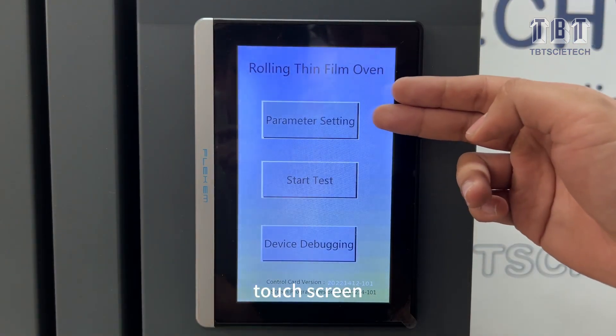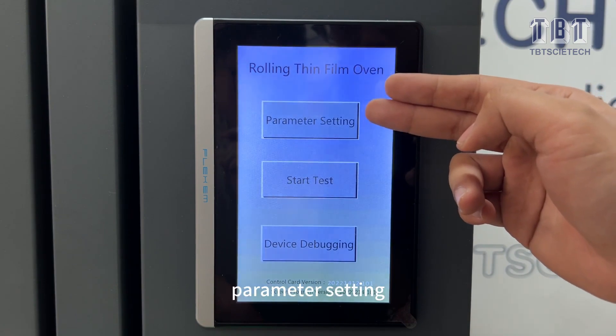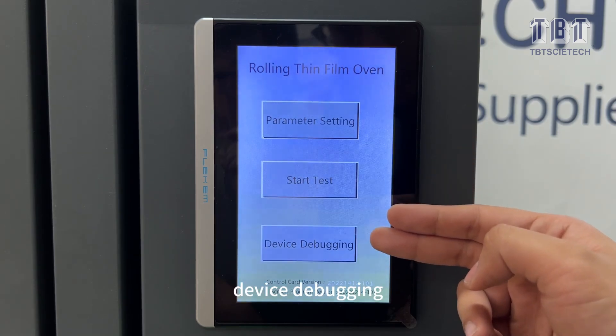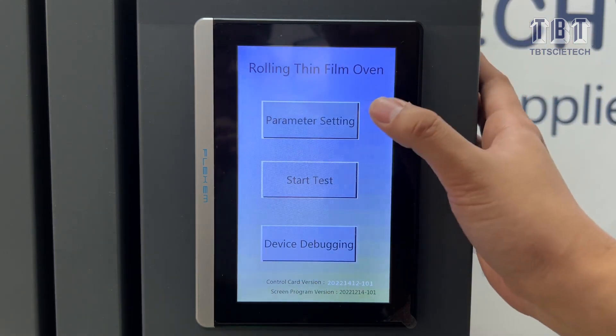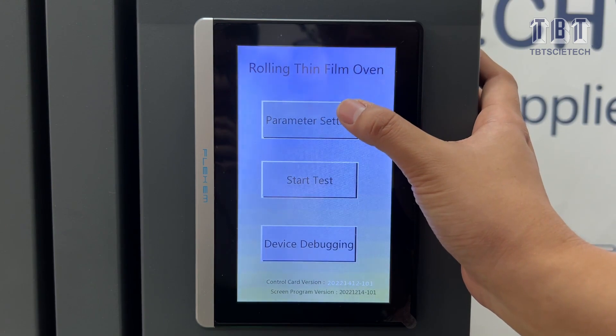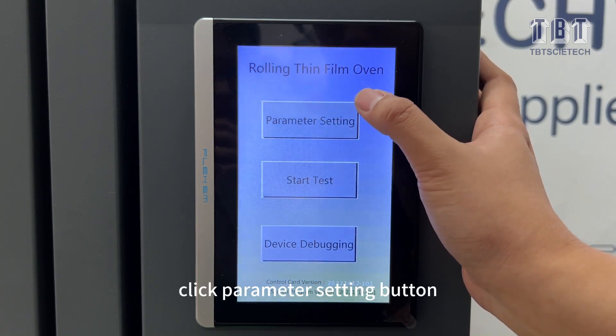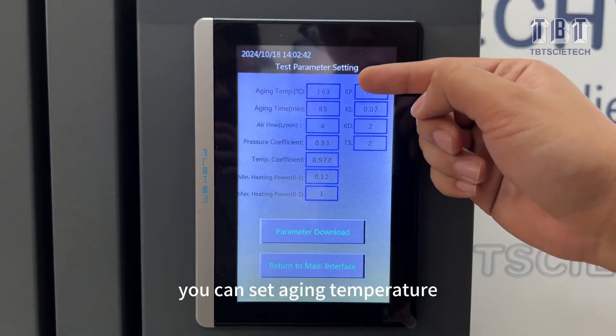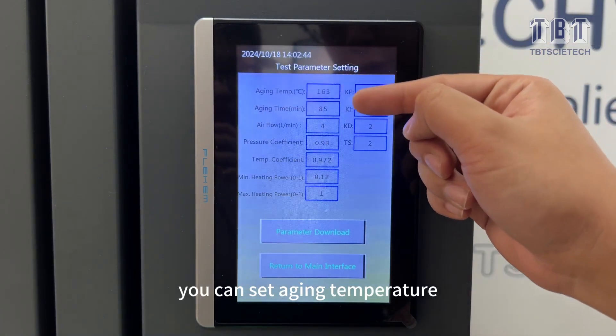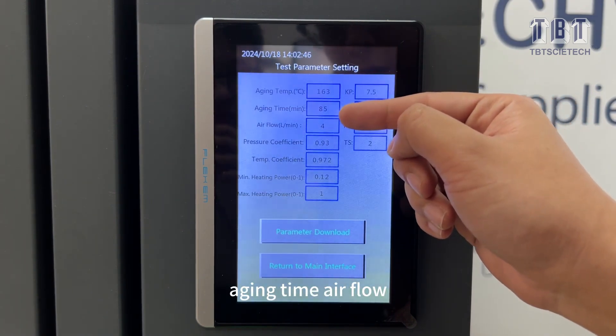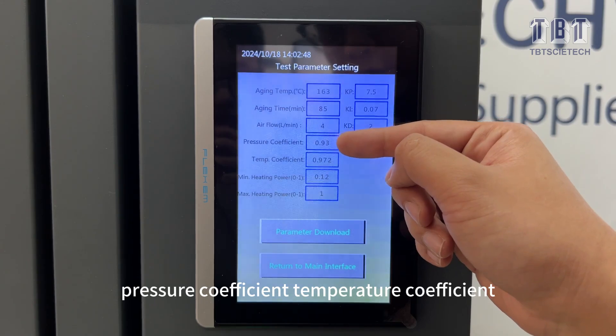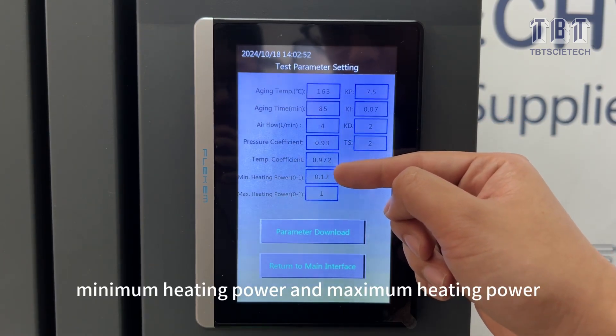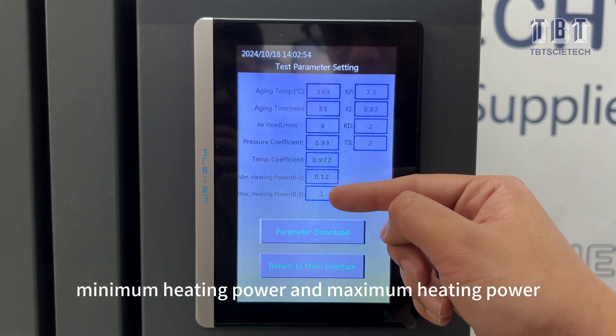On the touchscreen, you can access parameter setting, start test button, and device debugging. Before the test, click the parameter setting button. You can set aging temperature, aging time, airflow, pressure coefficient, temperature coefficient, minimum heating power, and maximum heating power.